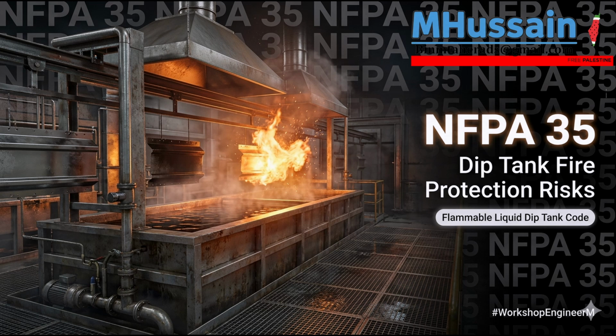Okay, how does that system work in practice? The facility must be equipped with optical or catalytic sensors that constantly sample the chemical composition of the air right in the exhaust ducts. As long as the concentration of flammable vapors remains below 25% of the lower flammable limit, the LFL, the system can safely recirculate. So that 25% threshold gives you a massive 75% safety margin before the air actually becomes explosive. Exactly. But if a spill occurs and the vapor concentration spikes above that 25% limit, the system must trigger an automatic, immediate physical response. Like what? It sounds an alarm. Motorized dampers instantly slam shut to block the recirculation path, and the system diverts to 100% full exhaust directly to the outside atmosphere.